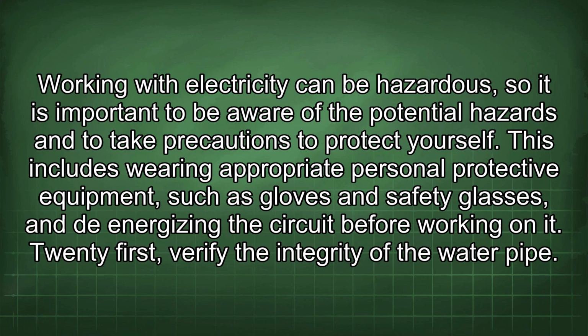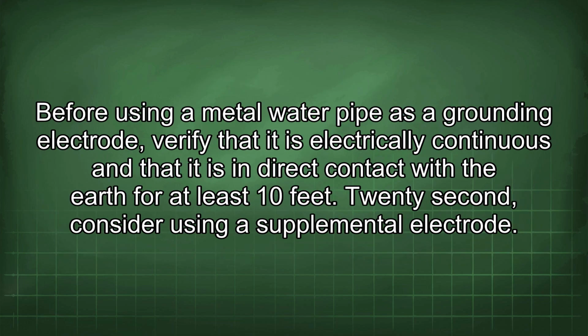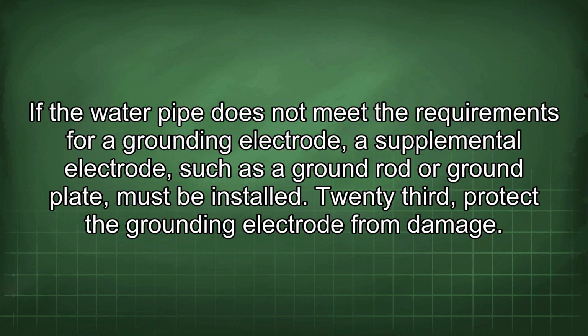21st, verify the integrity of the water pipe. Before using a metal water pipe as a grounding electrode, verify that it is electrically continuous and that it is in direct contact with the earth for at least 10 feet. 22nd, consider using a supplemental electrode. If the water pipe does not meet the requirements for a grounding electrode, a supplemental electrode, such as a ground rod or ground plate, must be installed.